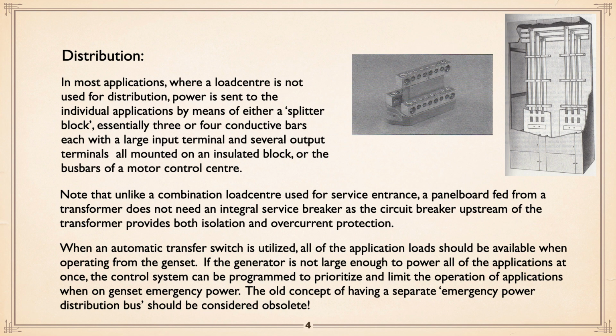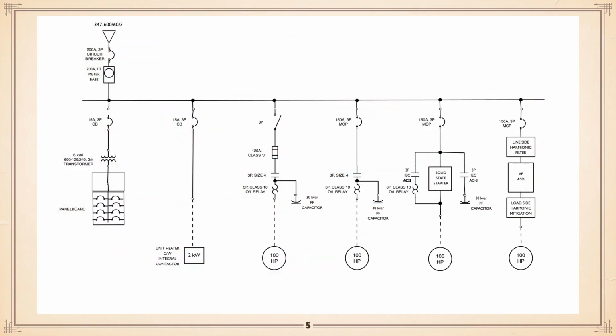Okay, the emergency power distribution bus, I say I don't like that old approach. Now, here's a typical power distribution drawing, although it's made up more for show than go, showing incoming 600 volt. The main circuit breaker could be fused. Again, you're over current. Your meter base, we're assuming it's 200 amp or below, and it's distributing. And the first one shows us going through a 15 amp breaker to a transformer, which actually should be 600 to 120/208 three phase, a panel board, and then from the panel board you distribute your various loads, either 120 or 208, single or three phase at 208.